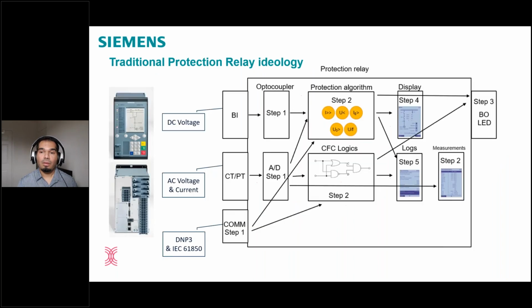So before we deep dive into how the SIPROTEC digital twin works, how everything goes on with the application, let us first look at how a traditional protection relay works. A traditional protection relay will have both hardware and software aspects that come together to form a protection relay. You have binary inputs, which is BI, which can be used for statuses or defining user inputs. You have CTs, PTs, current transformer and voltage transformer inputs, which are secondary inputs, which will be responsible to measure the actual currents and voltages in the power system.